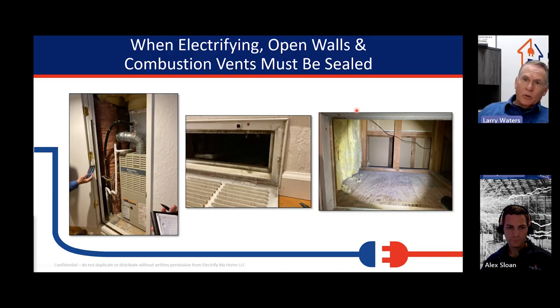When you're electrifying, we must close up open walls, and combustion vents must be sealed. If we're taking a furnace out of a furnace closet and we're sliding a new heat pump air handler into there, we need to take that opportunity to close off the intake and exiting combustion vents. We need to seal around the base where the drywall doesn't quite meet the plywood. We need to seal around that. We need to seal around any penetrations coming through the walls.